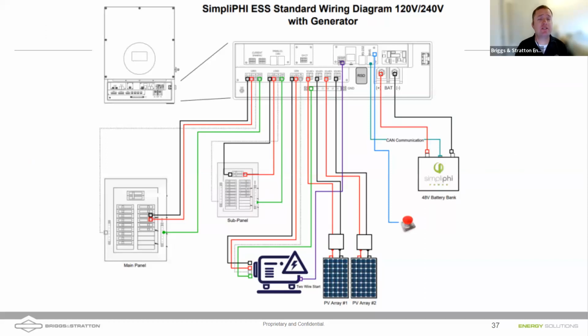Yeah, that's a good question. When these generators start up, the inverter is going to qualify that signal and take a look at it. If it likes what it sees and it's within the parameters that the inverter has set into it, it's going to go ahead and start charging from that. It's hard for me to know every different generator model out there, but let us know your model, and we can talk to some of our sales application engineers and look at the specifics of it. But I'll say this: if it's an old dirty generator sine wave, it might not.